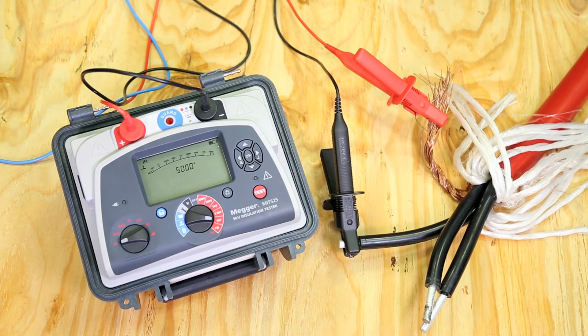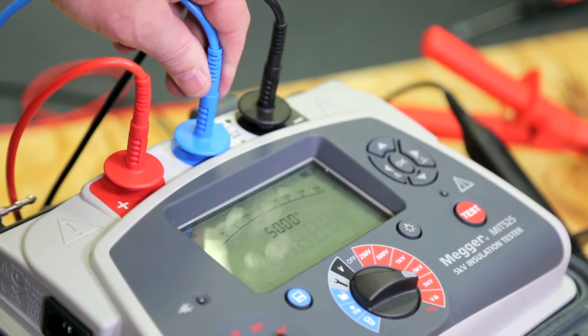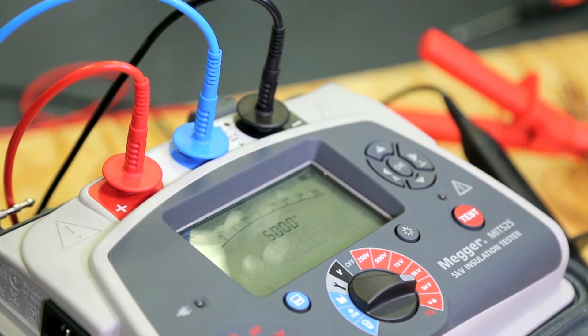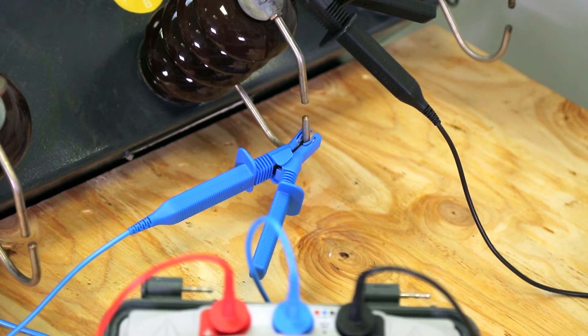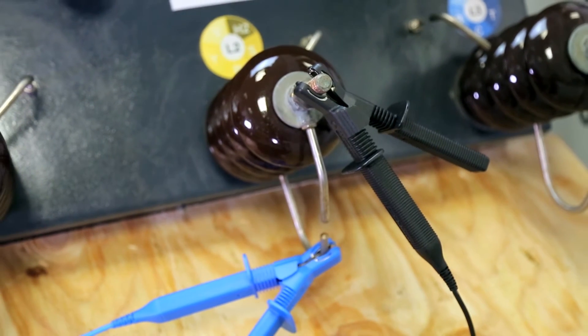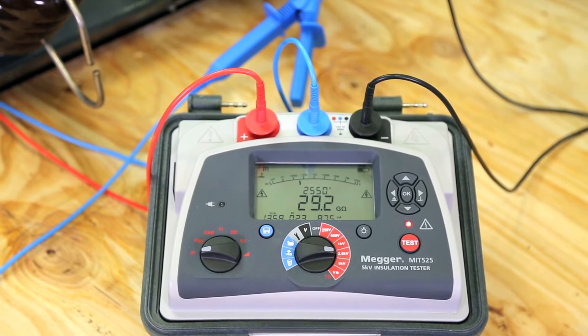If the test leads disconnect it could be extremely hazardous. The guard terminal ensures you measure the insulation that you want to measure. It measures and discounts any surface leakage current, and is key to the accuracy of the insulation test. That's why Megger's guard terminal performance is specified and offers unmatched accuracy.